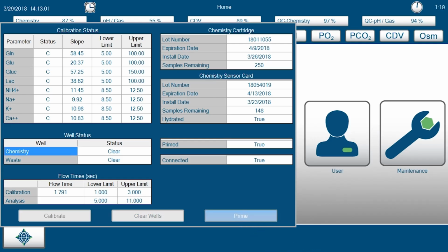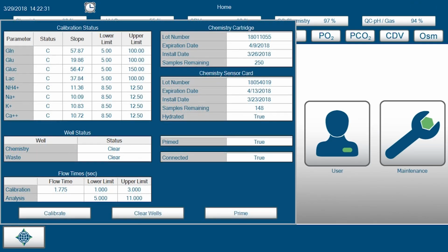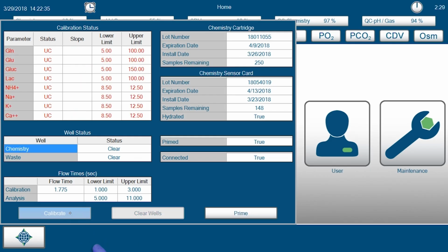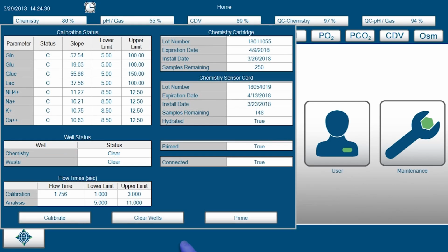Calibrated parameters will show C in the status column, and a red UC if it is uncalibrated. If any parameter is uncalibrated, you can calibrate the module by selecting the Calibrate button. The well status must be clear for the module to be available. If the well status displays blocked, select the Clear Wells button.